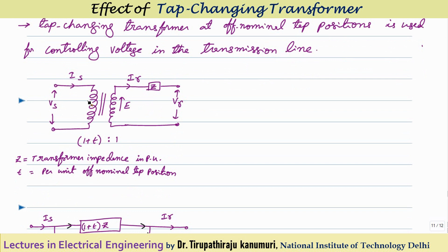The advantage of providing tappings on the high voltage side is that the current is less, so sparking will be less when changing. Also, on the high voltage side the number of turns are more, so changing one turn allows fine tuning of the voltage. That is why tapping changes are always provided on the high voltage side.